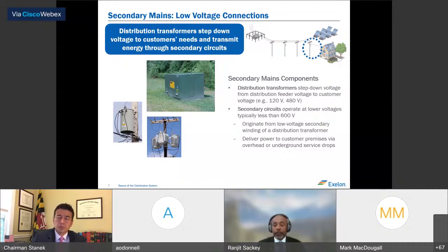And then at the end of the primary system, we have service transformers or distribution transformers. These step down the medium voltage of the feeder to low voltage for consumption of the customers. And this is that transition point between the primary and the secondary system. These transformers can be pad mounted. The example of that is the green box in the larger picture here, or they can even be submersible for underground distribution systems, or they can be pole mounted, as you see in the other two pictures. And then we have secondary lines or low voltage lines to transport the energy from the transformers to the customer premises.